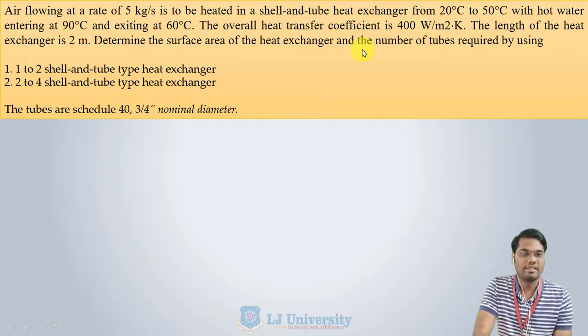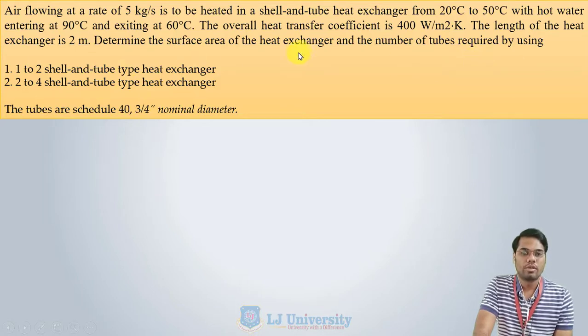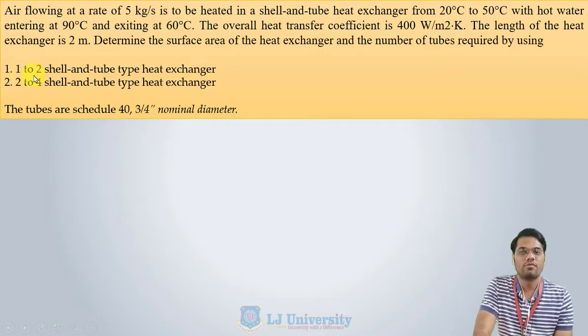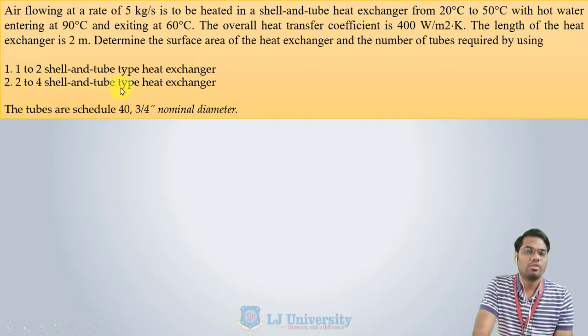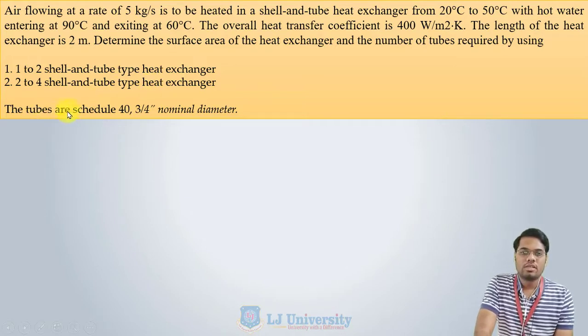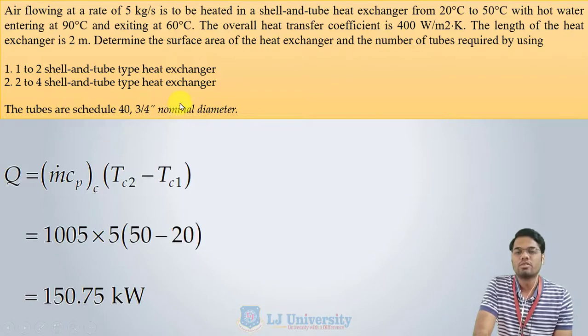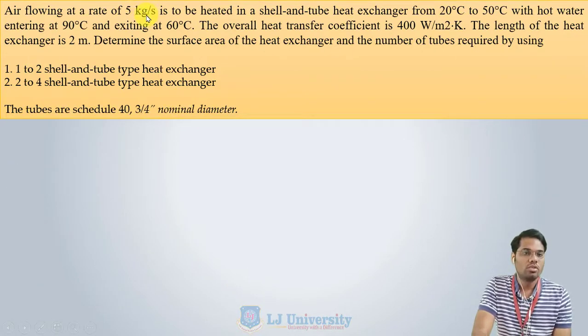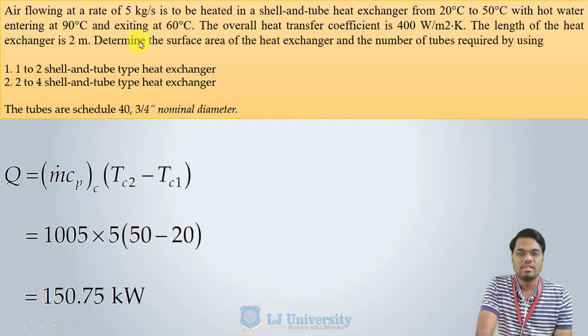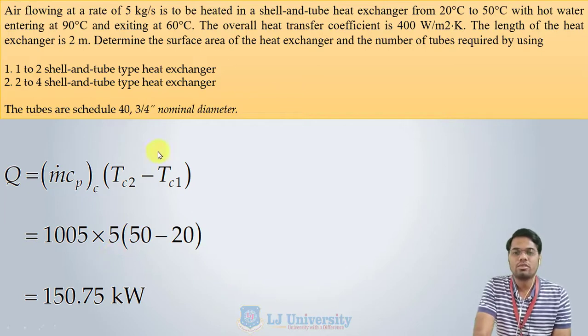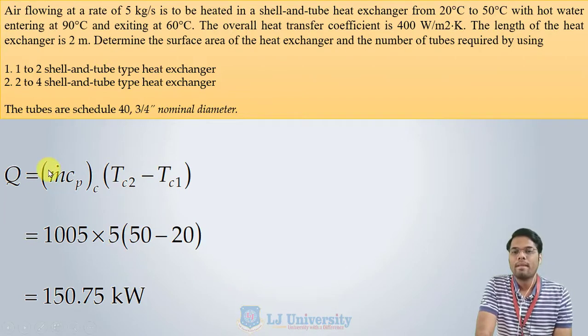We need to determine the surface area and the number of tubes required. This numerical is solved for two configurations: first, 1-2 shell and tube type, and second, 2-4 shell and tube type. Since we know TC1, TC2, and the mass flow rate of the cold fluid, we can calculate Q using the energy balance equation. We can also find the unknown mass flow rate of the hot fluid, but that is not required right now.